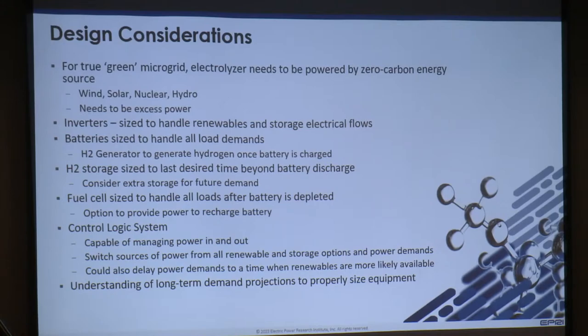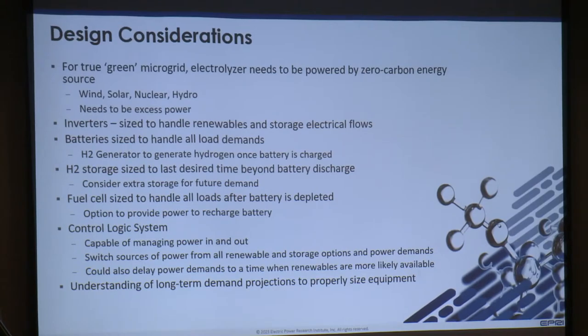So you're kind of defeating the purpose of having a green microgrid. Your inverters need to be sized to handle the renewables and the storage electrical flows. Batteries need to be sized to handle all demands, and the hydrogen generator can be used to generate hydrogen once a battery is charged. So the hydrogen storage needs to be sized to last the desired time beyond the battery discharge.